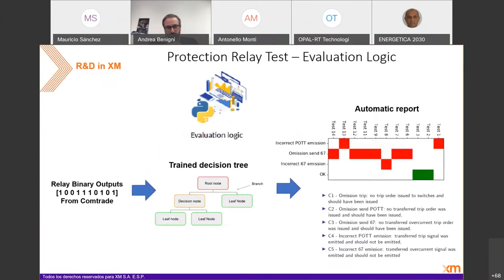How do we do that? We design a decision tree algorithm that learns from previous operation and is prepared to judge the binary inputs that were read from the Comtrade files stored by the relay in every case, determining if the behavior of the relay was as expected or not.